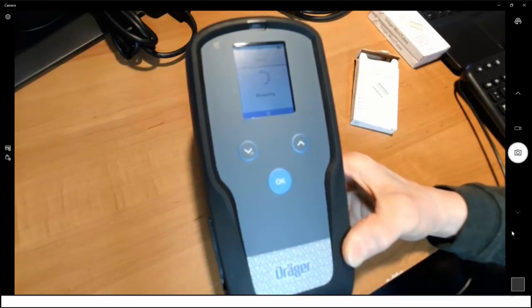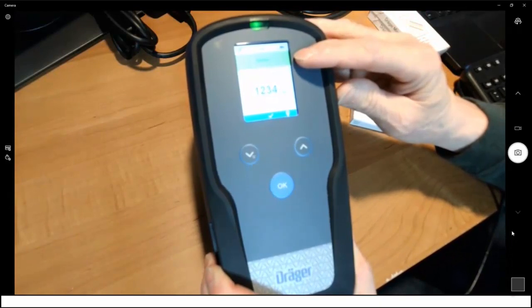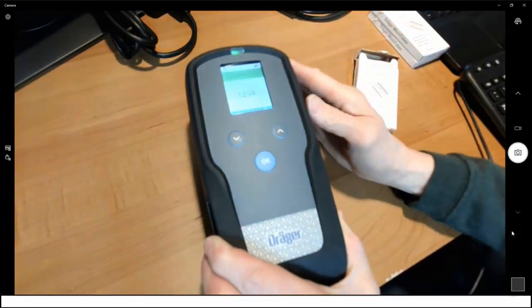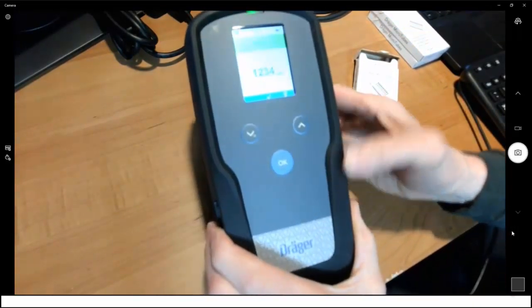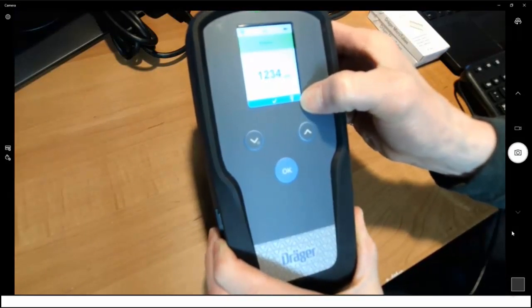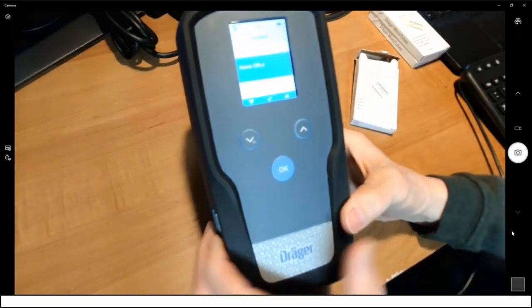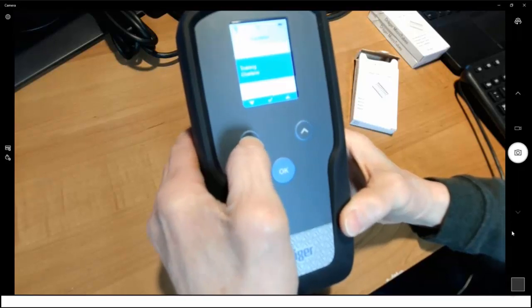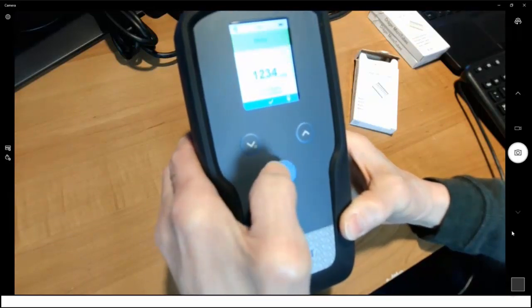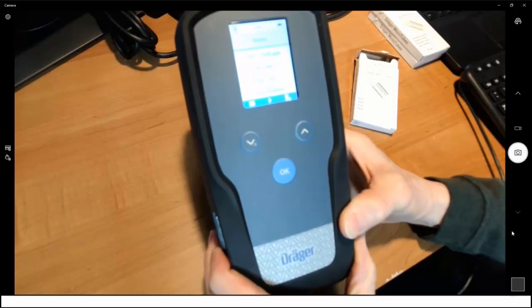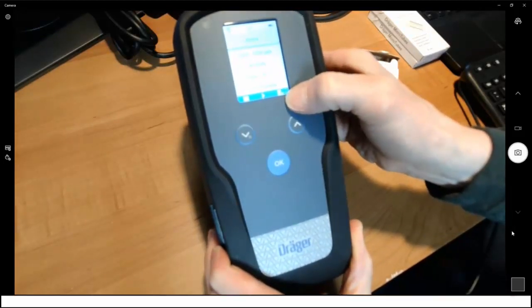Each time the screen goes down we need to press the OK or any of these buttons to bring the light back up. Once the light is on we can then proceed either into the menu, eject the microtube, or to commence with a measurement as I'm about to do. So now we have in the display that is actually taking a measurement. As I say this is a demonstration so it runs for roughly 20 seconds just to show the basic operation principle behind the system. At the conclusion of the measurement we have the green LED illuminated also the bar behind the analyte in this case it reads demo turns green so the operator understands the measurement has been completed. The device also have the sort of GPS coordinate symbol over here that's the means by which we can access the data logger and I can use this arrow to scroll down I'm going to scroll to North Huntington Pennsylvania I'm going to select that. It then tells me measurement result the location code and I acknowledge it.